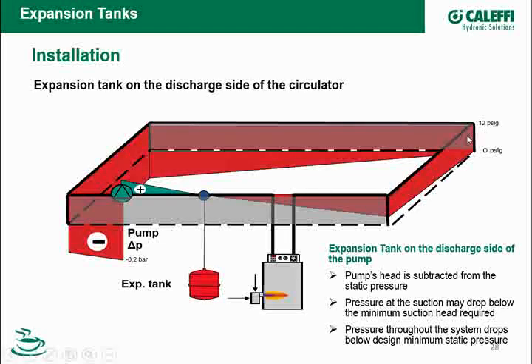First off, I've decided 12 psi in this is my minimum static pressure on the system. With that locked in at the discharge side of the pump, now the dynamic losses take place, and as I move around my hydronic system loop, my pressure starts to decrease and drop below that 12 psi point until I get around to the inlet side of the pump, where I'm now at the full delta P, or differential, of that pump. The other thing that happens is the pump suction pressure drops based on the delta P of that pump. I may all of a sudden get into a cavitation problem because I've dropped my suction pressure below the minimum design suction pressure for that pump.